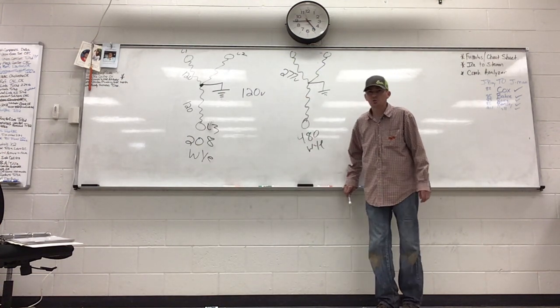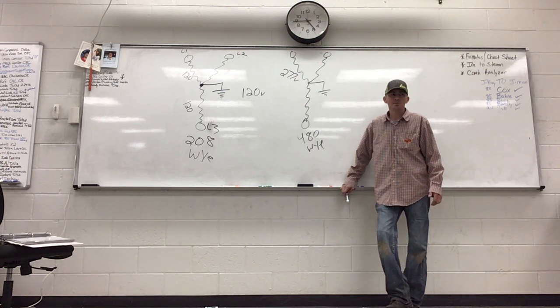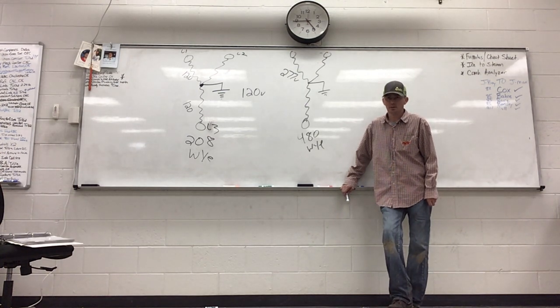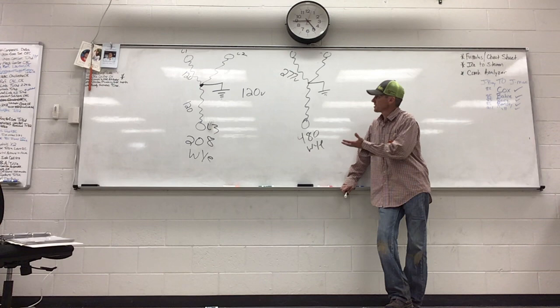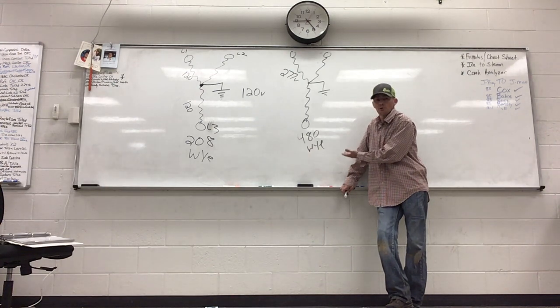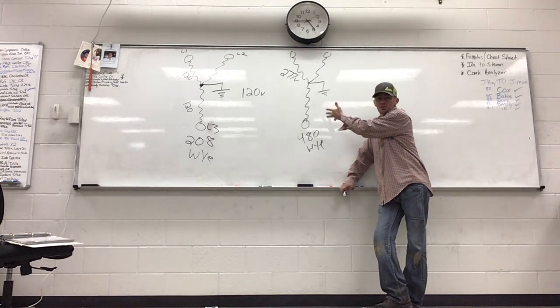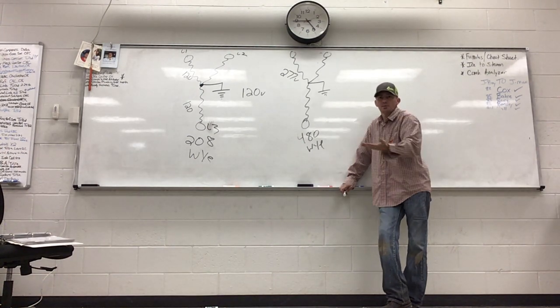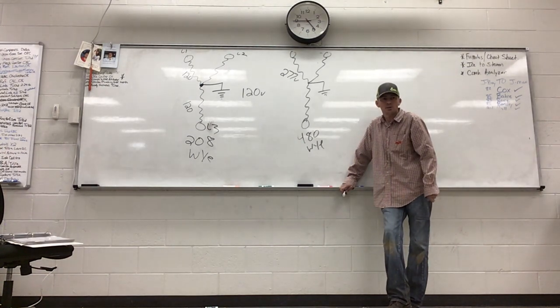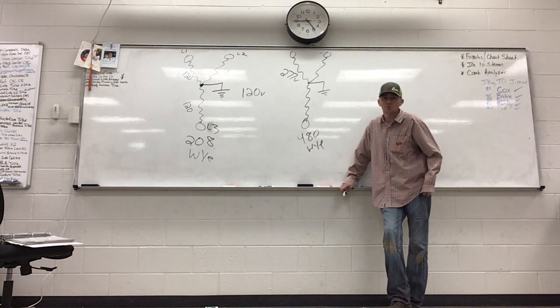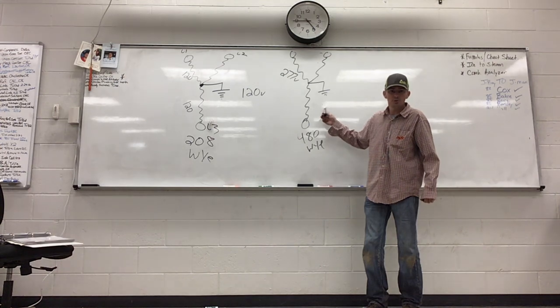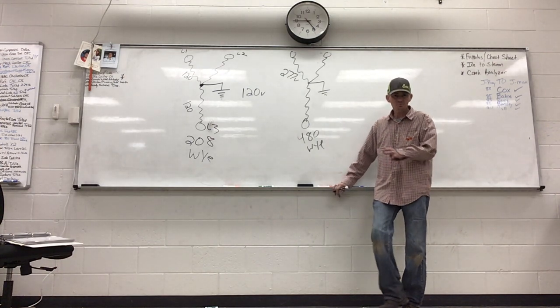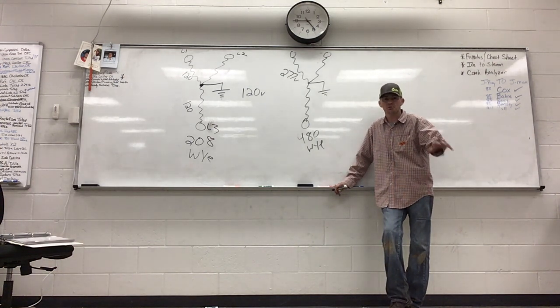Do not try to run a 240 volt motor on 277. Like, that's stupid. Don't do that. So how do you get 120 volts in this building, right? You can't, there's no 120 volts feeding this building most of the time. You can't get a 277 volt computer that I know of, or a 277 volt pencil sharpener. So the only way that we get 120 volts in these buildings is we have to set additional transformers.